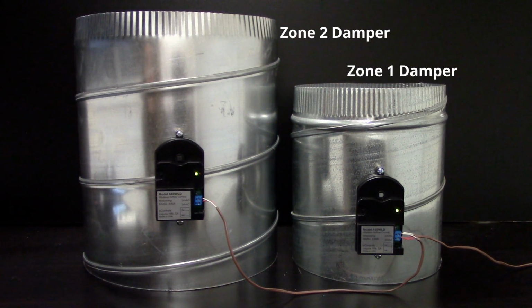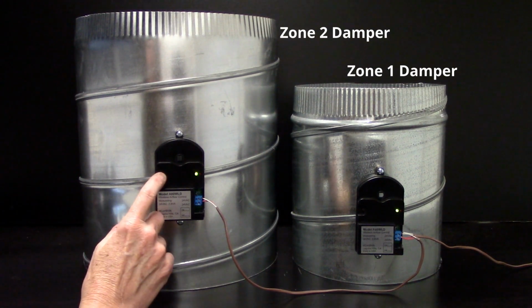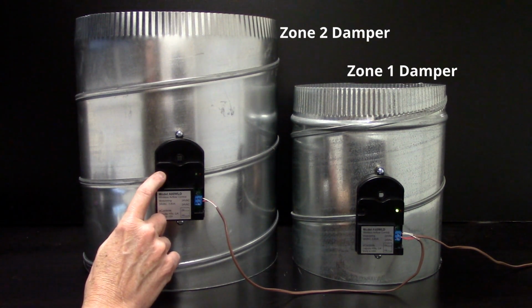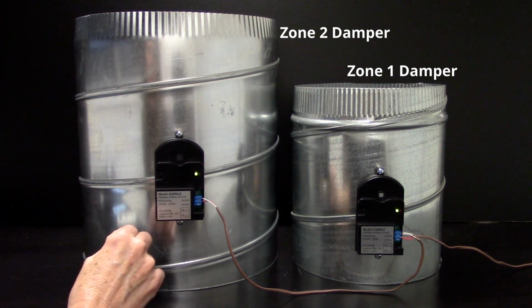It's important to note that the WRCD wireless remote damper control is not intended to be used as a zoning system, and caution should be taken when controlling multiple spaces. First, the zone number needs to be set in the damper actuator. Press and hold the push button on the actuator. The green LED blinks once, pauses, then blinks twice, pauses, then blinks 3 times, and so on up to 8 blinks. Release the push button after the number of blinks corresponding to the zone number to be set.